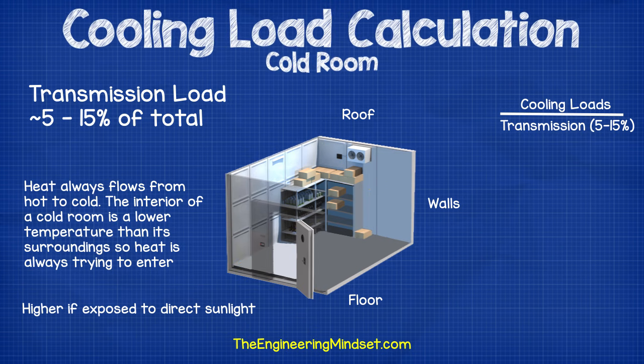So where does the heat come from that we need to remove? Well, typically 5 to 15 percent is through transmission loads. This is the thermal energy transferred through the roof, the walls and the floor into the cold room. Heat always flows from hot to cold, and the interior of the cold room is obviously a lot colder than its surroundings, so heat is always trying to enter the space. If the cold store is exposed to direct sunlight then the heat transfer will be higher, so an additional correction will need to be applied.